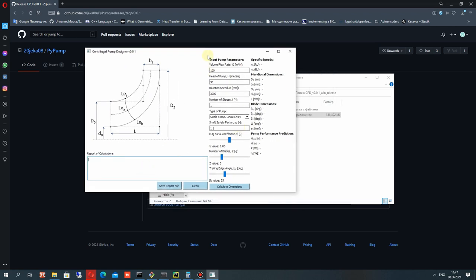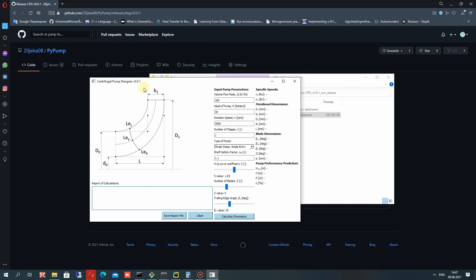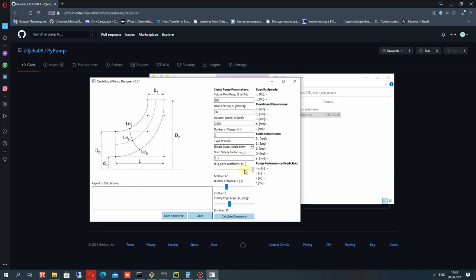Here we can see the CPD program. On the left side you can see the scheme showing what each dimension means — D0, D2 for example. The input parameters are: the volume flow rate of the pump, the head of the pump in meters, the rotation speed of the rotor impeller. Additional inputs include the number of stages — which will be single stage since it equals one — and the safety factor for the shaft, which defines the shaft diameter.